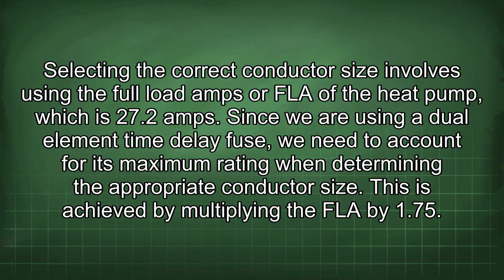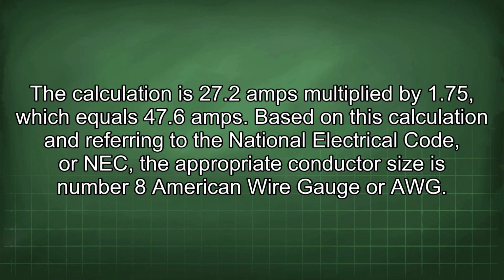Selecting the correct conductor size involves using the full load amps, or FLA, of the heat pump, which is 27.2 amps. Since we are using a dual element time delay fuse, we need to account for its maximum rating when determining the appropriate conductor size. This is achieved by multiplying the FLA by 1.75. The calculation is 27.2 amps multiplied by 1.75, which equals 47.6 amps.